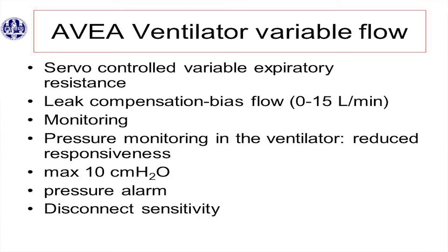Sounds good. That's what I always thought. But when you look closer, I made a recording of an infant. This is just a random infant that was on CPAP in the unit. So the set pressure is 8. It receives 7. And you see there's a fast response on the flow. But even then, the maximum flow setting is already reached.